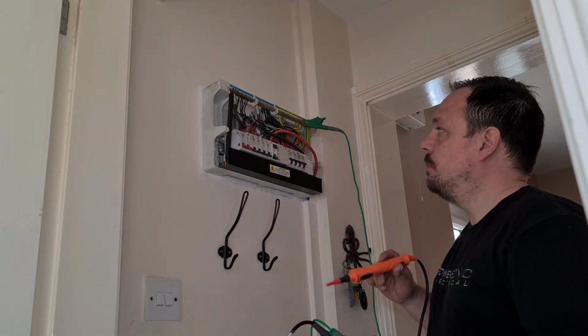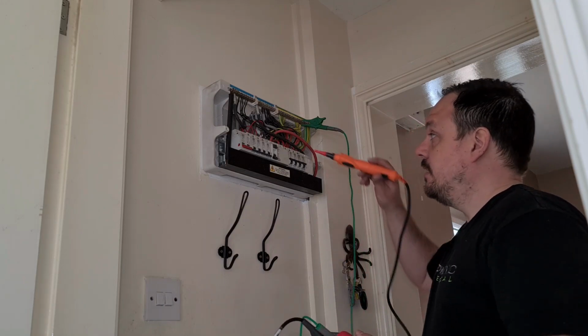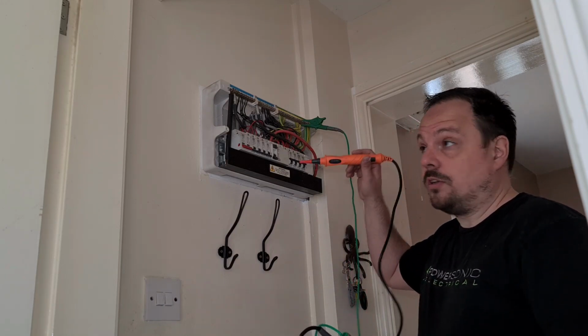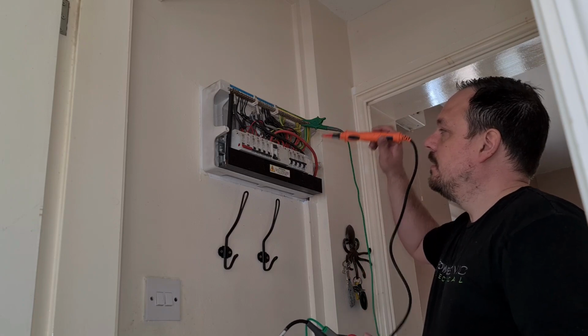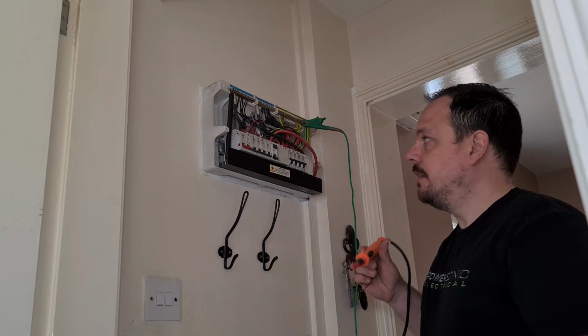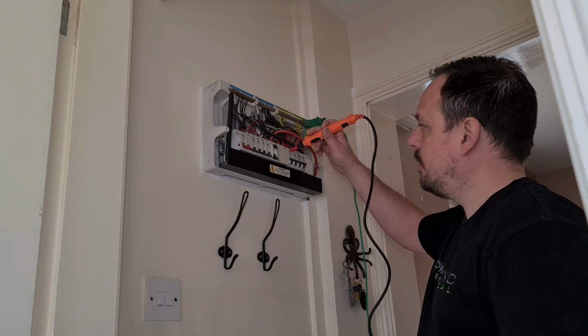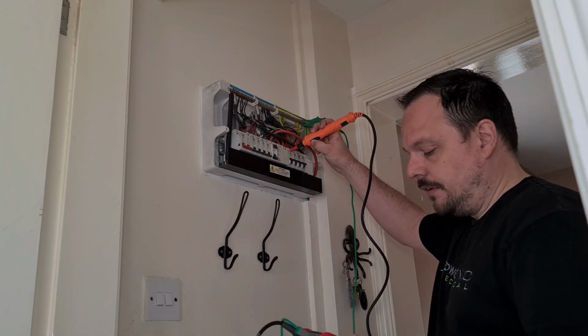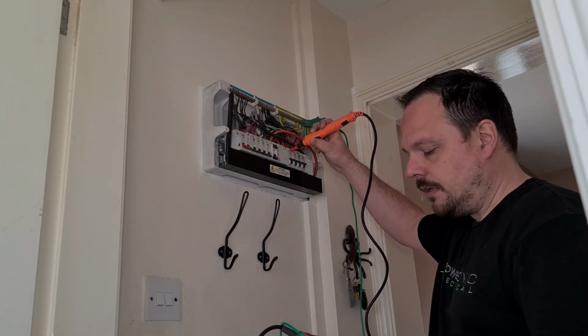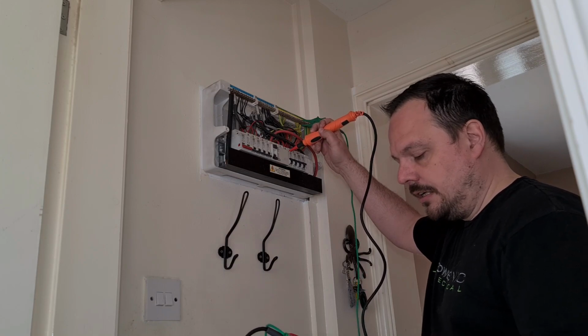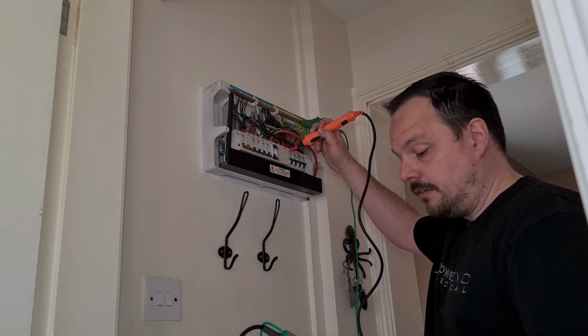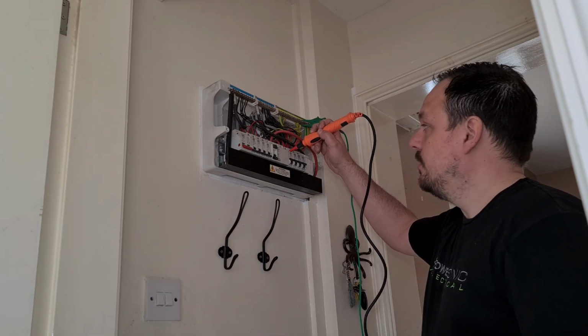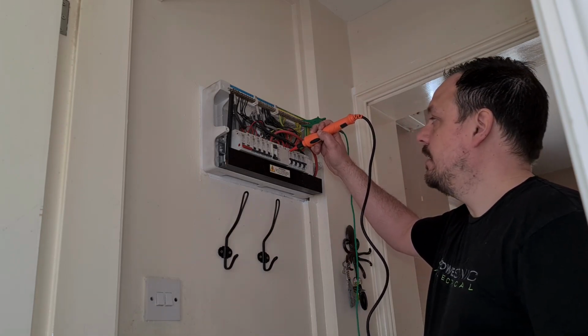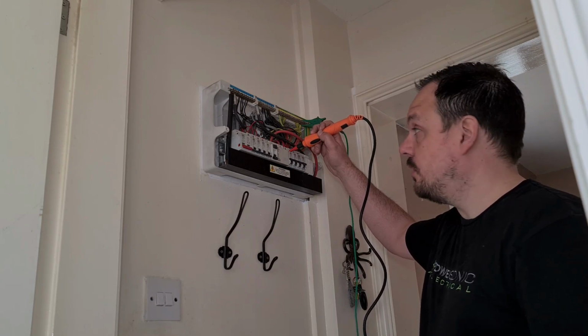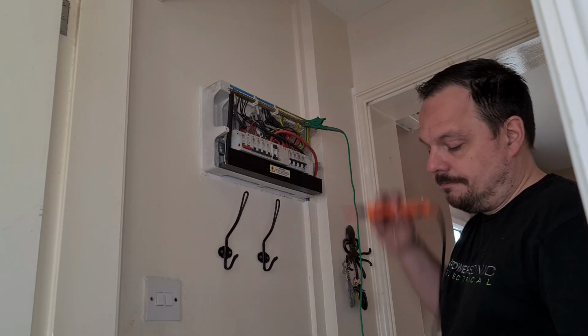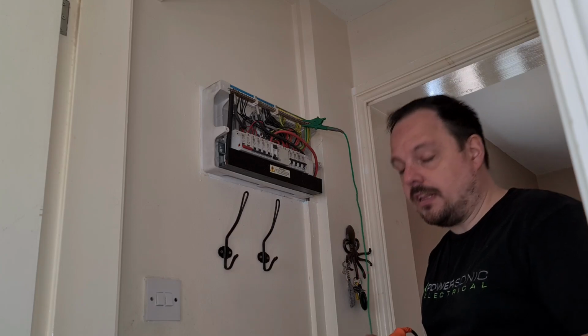Put our crock clip up onto the earth bar, and you can test all of those in one go to the IR value between your line and your earth. You do that just by going onto any one of these that you wish. If you hit the test button, it'll start applying that voltage. And I am measuring clear of 500 megohms. So it's saying we don't have any issue between the line and the CPCs on those socket circuits. So it's quite happy with that.